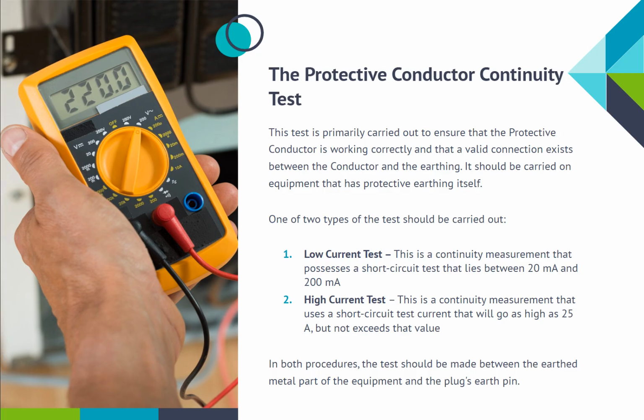1. Low current test. This is a continuity measurement that uses a short circuit test current between 20 mA and 200 mA. 2. High current test. This is a continuity measurement that uses a short circuit test current that will go as high as 25 amperes, but not exceed that value. In both procedures, the test should be made between the earthed metal part of the equipment and the plug's earth pin.